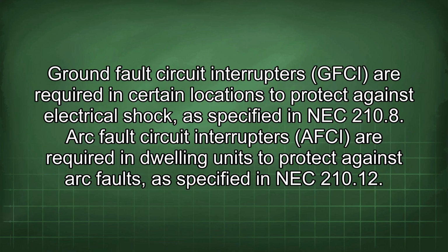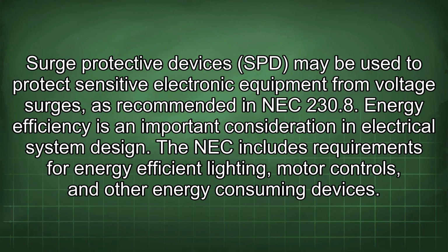Ground fault circuit interrupters (GFCI) are required in certain locations to protect against electrical shock, as specified in NEC 210.8. Arc fault circuit interrupters are required in dwelling units to protect against arc faults, as specified in NEC 210.12. Surge protective devices (SPD) may be used to protect sensitive electronic equipment from voltage surges, as recommended in NEC 230.8. Energy efficiency is an important consideration in electrical system design. The NEC includes requirements for energy-efficient lighting, motor controls, and other energy-consuming devices.